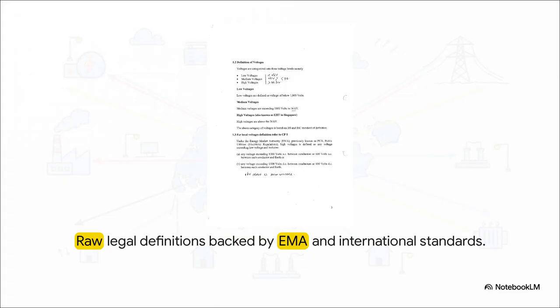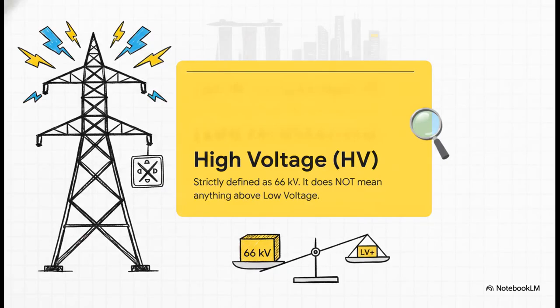And these categories aren't just industry shorthand. They have strict statutory roots. These legal definitions come straight from the Energy Market Authority, the EMA, and they align with international standards. This dictates everything from market rules all the way down to licensing. So there's a crucial point we really need to clear up right now regarding the definition of HV. In casual conversation, engineers might toss around high voltage to mean pretty much anything hotter than a standard wall plug. But in Singapore's formal system, HV legally and strictly points to that specific 66 kilovolt threshold. It is definitely not just anything above LV.